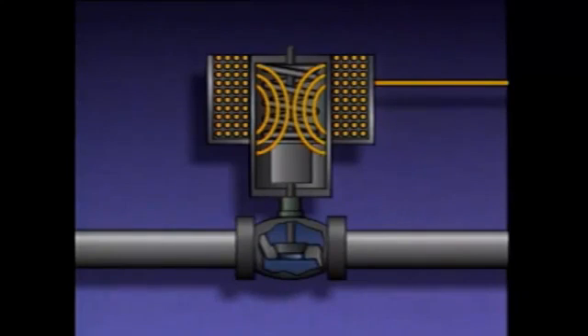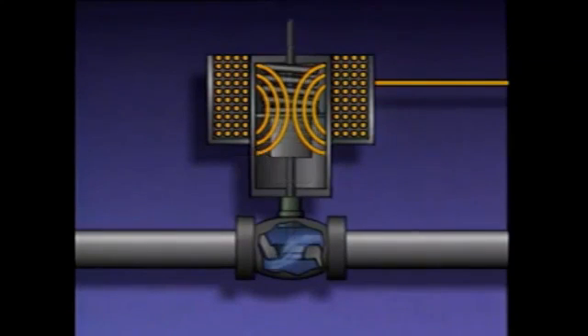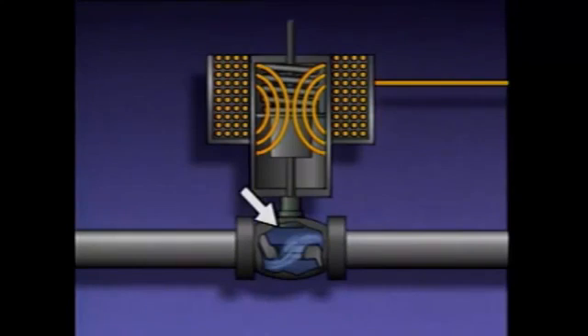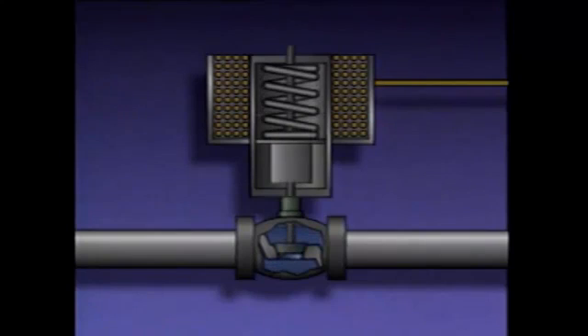When current flows through the wire coil, it creates a magnetic field around the coil, which in effect becomes an electromagnet. The armature, a solid metal core, is attracted to the magnetic field and pulled toward the center of the coil. As the armature moves, it compresses the spring and moves the stem, opening the valve. When current flow through the coil stops, the magnetic field is lost, allowing the spring to push the armature and stem back to their original positions.